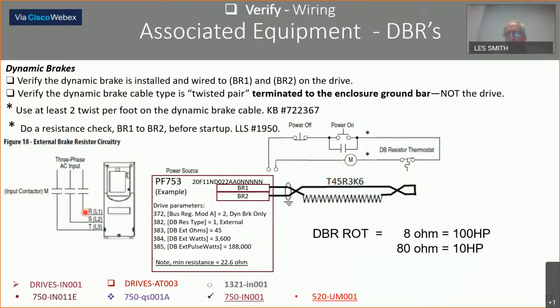This happened, let's just say 15 years ago. We had a power surge through mid-Ohio, and I lost 9 drives out at a customer's place because the chopper is still working even if the drive's not turned on. And we had power surges that went up above the threshold and turned on the dynamic braking resistors. It didn't happen to drives that had isolation transformers on them. But my customer lost a lot of drives and resistors. They burn them up.